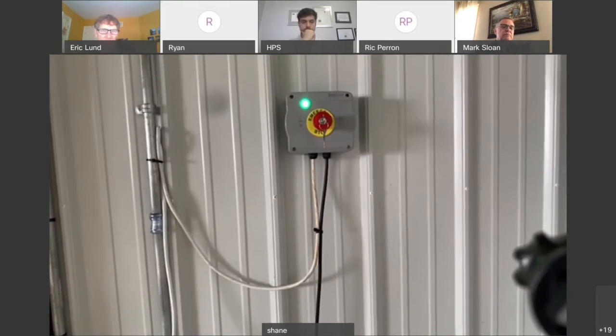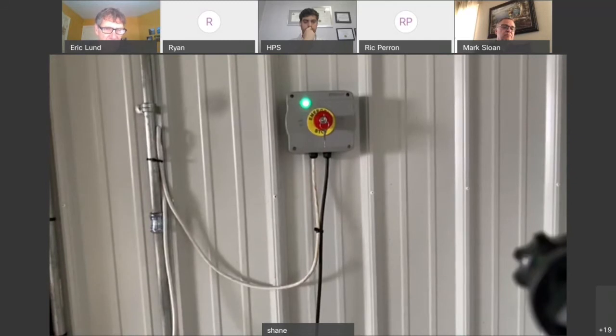Now that we lost our 120 input, let's say our inverter went dead because we hit a low voltage alarm and it doesn't turn back on. Well, that's never going to turn back on unless we are able to charge it via PV again, right? So we have to have a recharge voltage value that we can energize the rapid shutdown with, so that we could still be charging our batteries without an input. So instead of having a 120 to 24 volt step down, we will have a 48 volt to 24 volt, which will work off the nominal voltage of the battery bank.